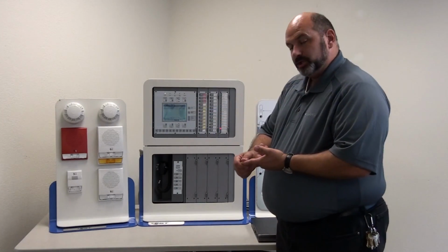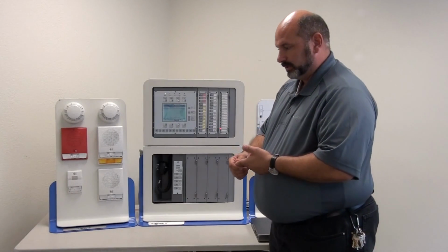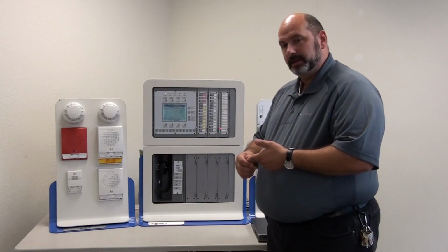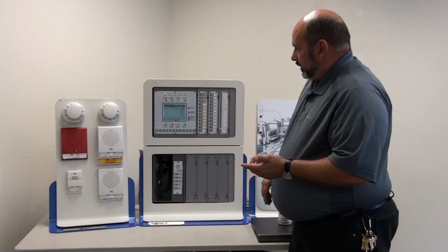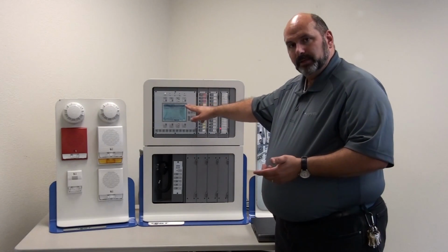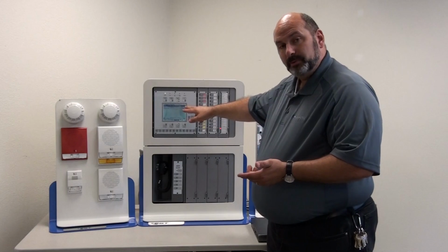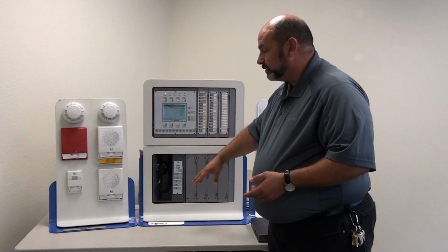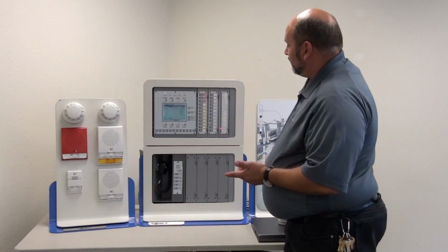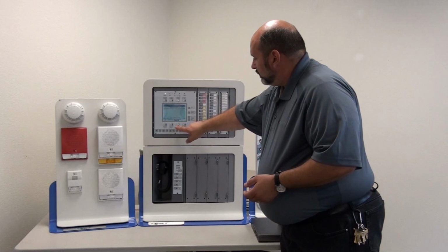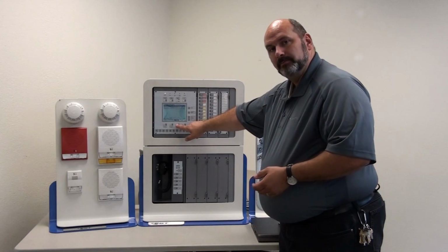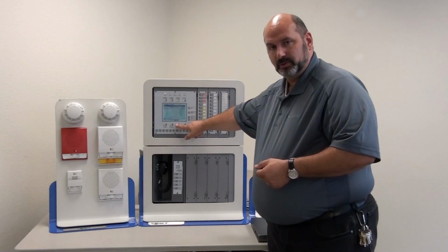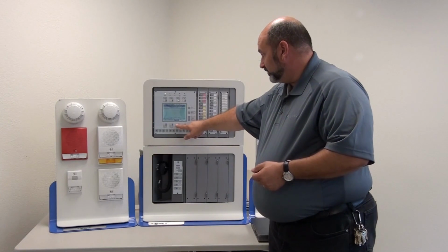Now, if you have a trouble condition on your panel, that means you might have something as simple as a loose wire somewhere, or there may be a dead battery in a power supply, or something of that nature. And when you come to a panel that's beeping and has a flashing light on it and says it's in trouble, you can press the panel silence button, which will silence any noise here at the panel. And you can press the trouble checkmark button down below the screen, and that will scroll through any number of different troubles that may be on the fire panel itself.